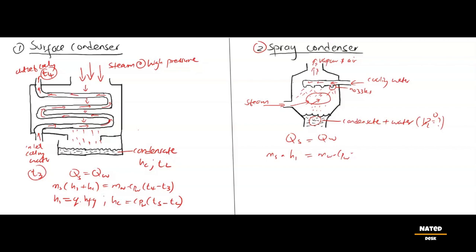In a spray condenser, we have inlet cooling water T3 but we don't have T4 outlet. Since water and condensate mix, instead we have what we refer to as the condensate mixture T4 or it will be given as the rise in temperature, change in T.